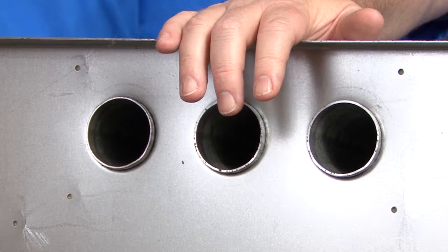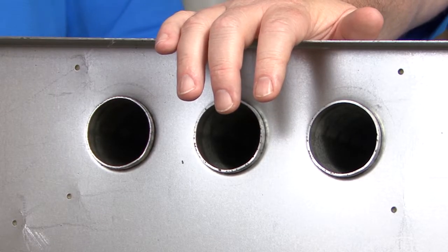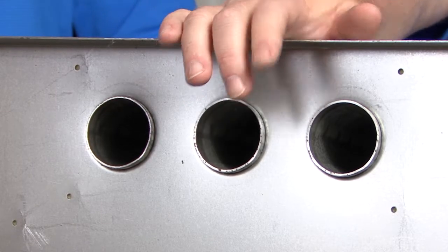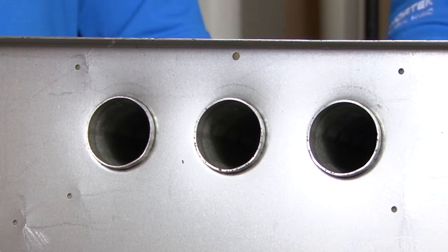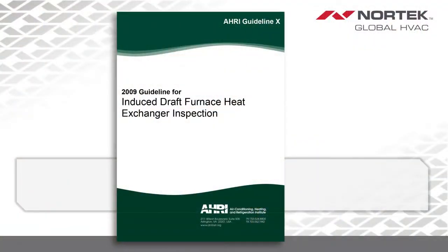And the two things that we're going to be talking about today are the two methods, if you will. One will be the introduction of smoke into the tubes of the heat exchanger onto the primary side as it starts to make its way through the primary side and working towards the secondary. The second will just be kind of a conversational description of the 2009 AHRI document for forced air induced draft heat exchanger inspection.